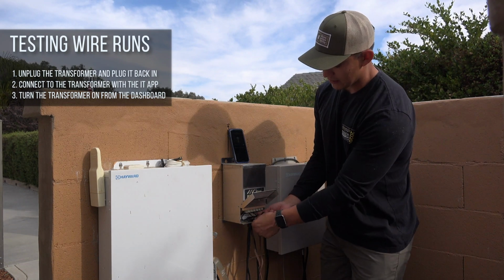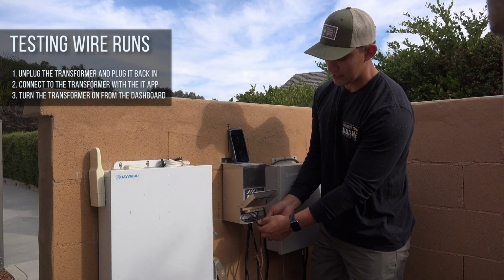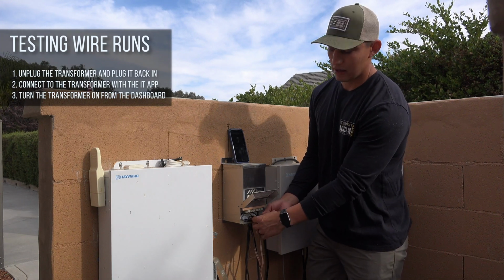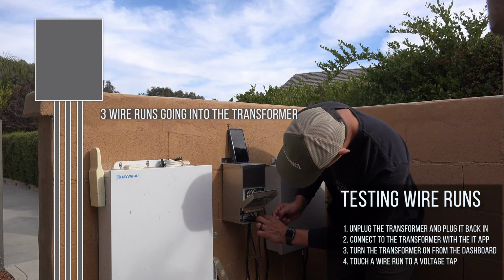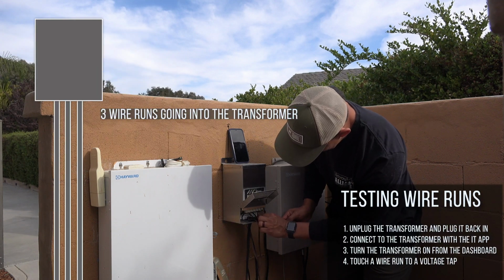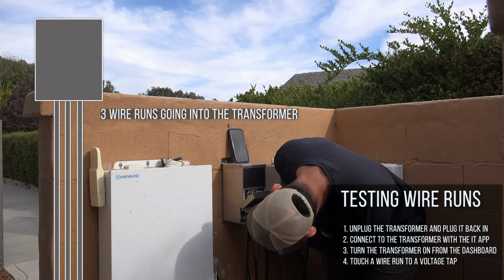What I've gone ahead and done is I disconnected from the volt tap all three wire runs, and all I'm going to do is simply push one wire run up into a tap to see if it trips the transformer.